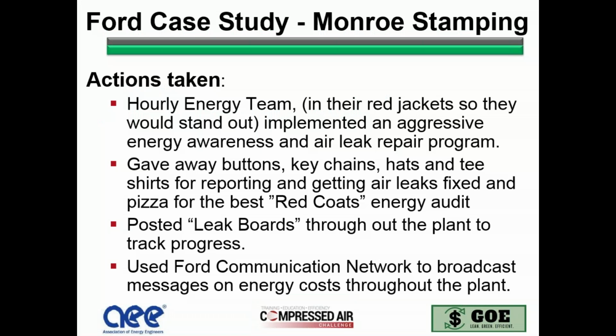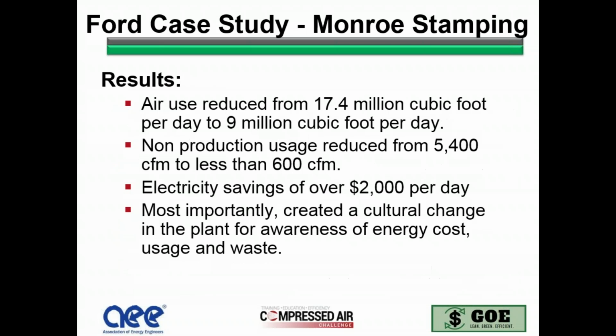The actions that they took, it was an hourly team. The plant manager got the team red jackets so they would stand out. They implemented an aggressive energy awareness and a leak tag program. They gave away buttons, keychains, hats, and T-shirts for reporting and getting air leaks fixed, and pizza for the best red coat energy audit when they would go do their audits on the weekend. They posted leak boards throughout the plant, and they used the Ford Communication Network, which were TV monitors in all of the break rooms, so they would broadcast messages throughout the plant.